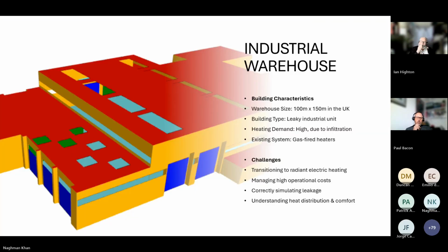Perfect. Okay, so this was a consultancy project that we took on sometime last year. It's an MOT bay warehouse that was using a lot of energy. The client thought it was very leaky, and they sent us photos of the building, and you could actually see daylight through most of the joins in the building. The doors to all of the bays are open most of the day, in various different configurations, and they wanted to decarbonize the building.